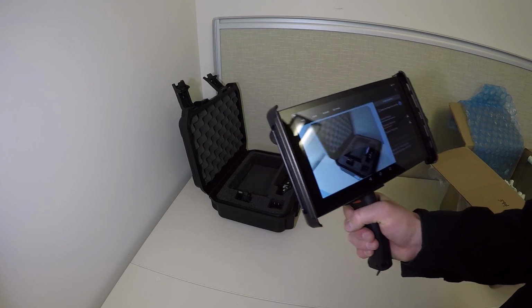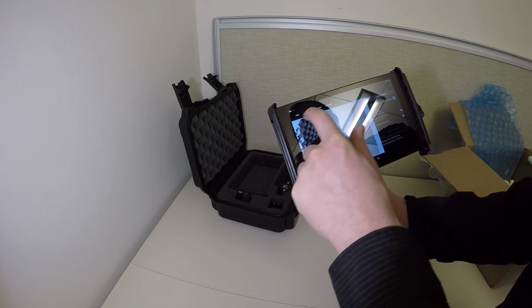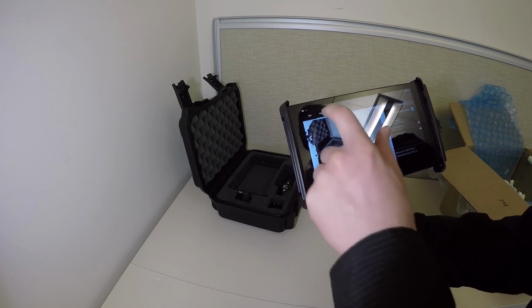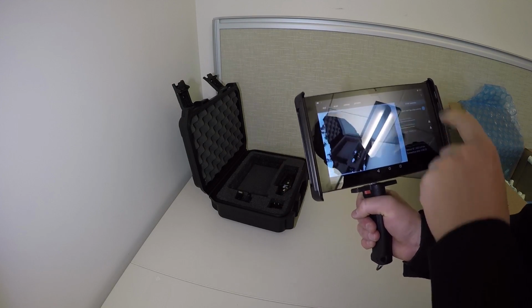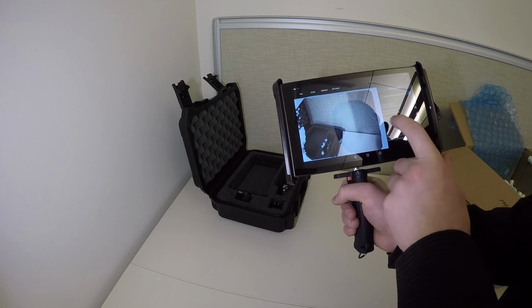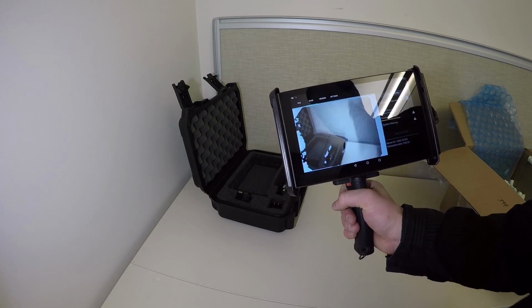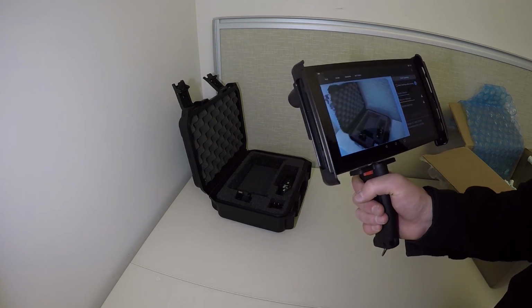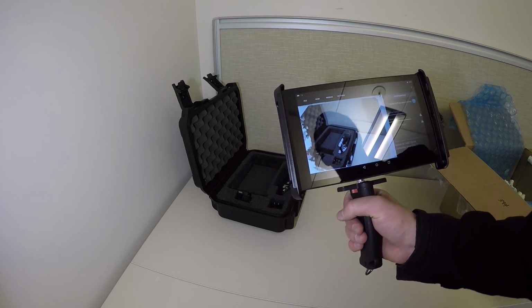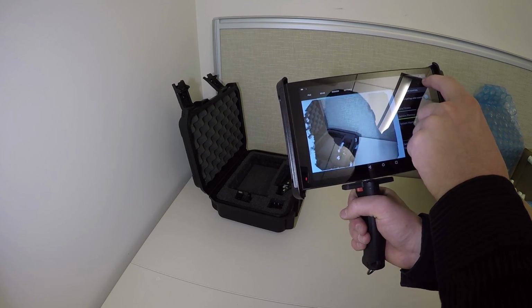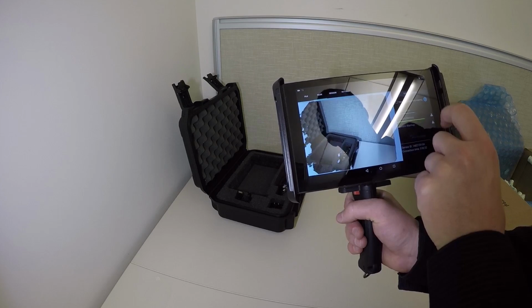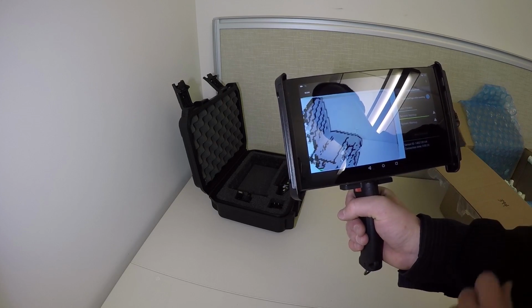In order to scan, you're already on the right page here: scan, file, session. So on the scan tab, you're gonna press start mapping, but you do have to wait for the warm-up time. It's about 15 minutes for the system warm-up and about 30 seconds for the session warm-up. As this is a demo here, we'll do a short warm-up time, start mapping.